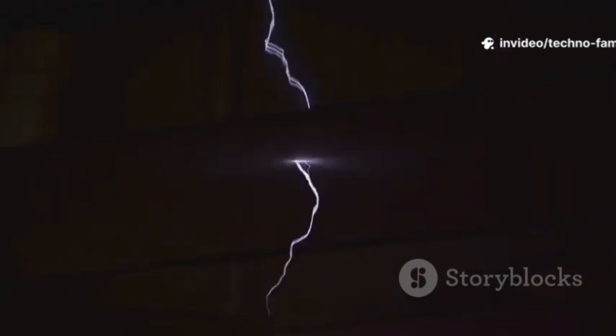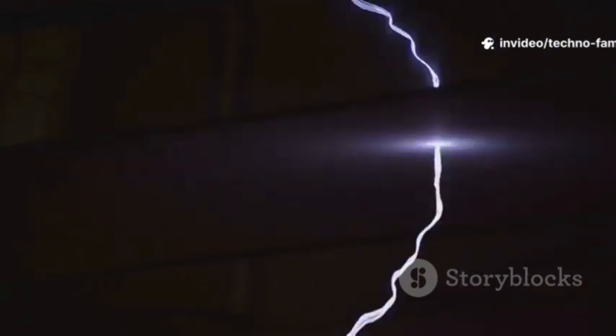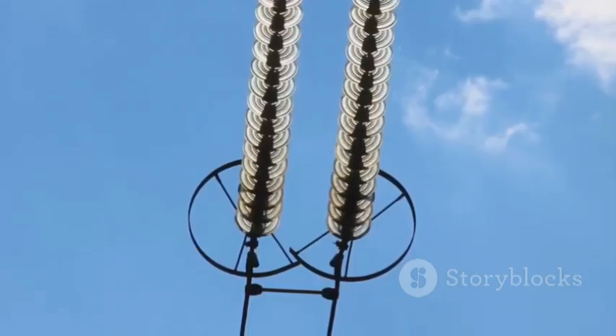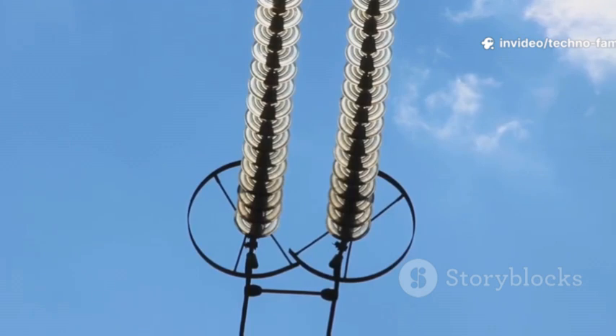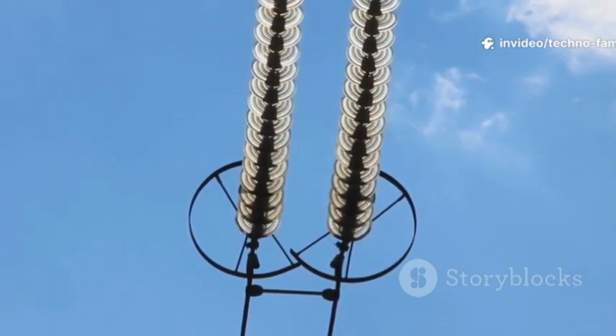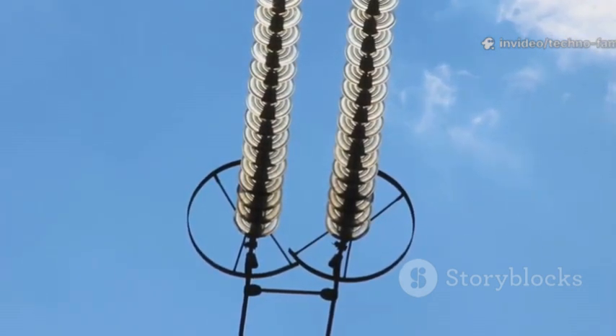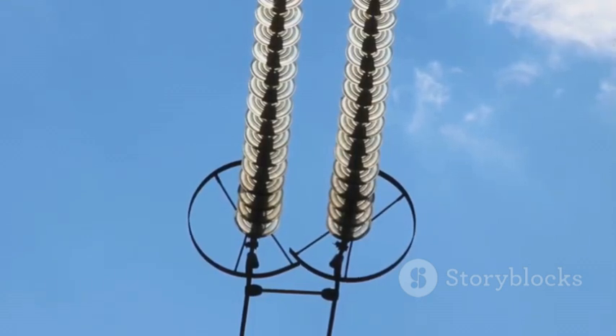Corona discharge: localized ionization of air when the field is strong near sharp edges, leads to noise, loss, ozone, etc. Design considerations and prevention: use insulation with higher dielectric strength. Proper shape and geometry, avoid sharp edges. Smooth electrodes, corona rings, control of environment.